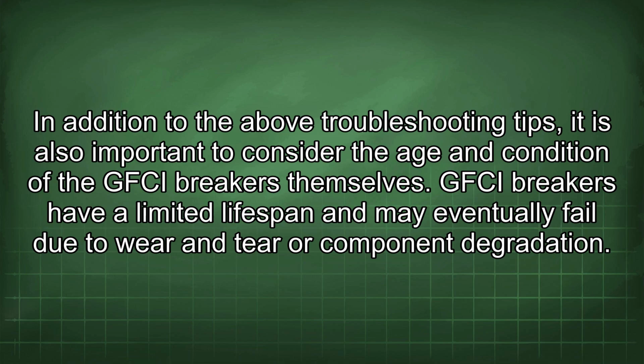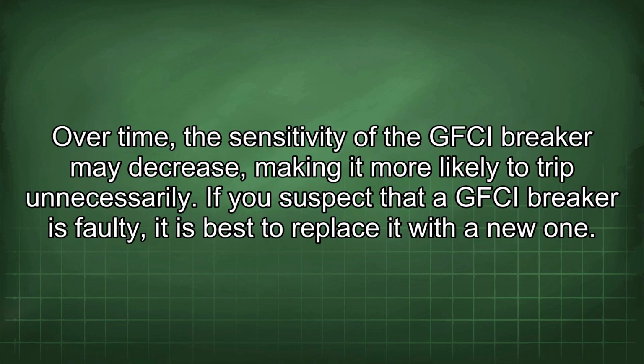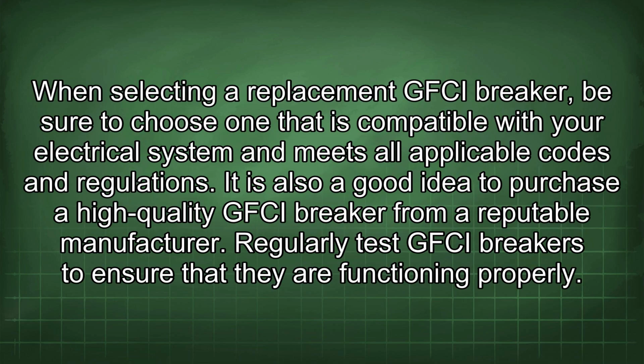In addition to the above troubleshooting tips, it is also important to consider the age and condition of the GFCI breakers themselves. GFCI breakers have a limited lifespan and may eventually fail due to wear and tear or component degradation. Over time, the sensitivity of the GFCI breaker may decrease, making it more likely to trip unnecessarily. If you suspect that a GFCI breaker is faulty, it is best to replace it with a new one. When selecting a replacement GFCI breaker, be sure to choose one that is compatible with your electrical system and meets all applicable codes and regulations. It is also a good idea to purchase a high-quality GFCI breaker from a reputable manufacturer.